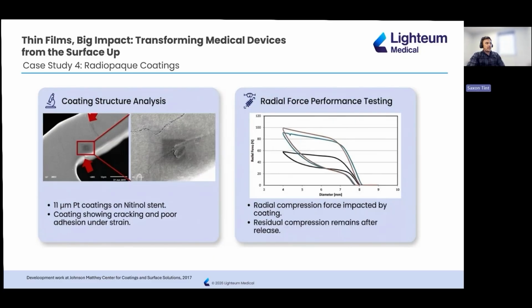So let's take a look at that platinum coated stent. When the stent is actually used, we see there are some problems. A stent isn't a static object. It's got to compress, flex, expand, and strain during deployment. Platinum is dense and radiopaque, and mechanically it's quite ductile, but it doesn't have anywhere close to the same elasticity as nitinol. So when the nitinol stent is strained, the platinum coating ends up cracking, delaminating, and spalling.